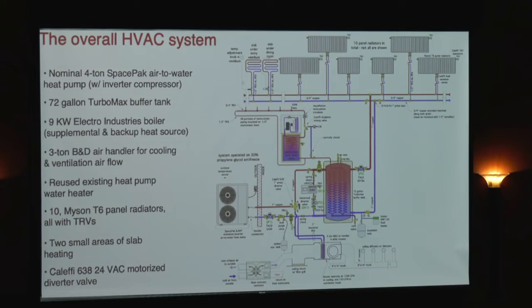So rather than do that, we had this girder that went right down the center line of the house, the full length of the house. It's a 12-inch deep laminated veneer lumber girder. You'll see it in just a minute here, basically we just hit the middle of that girder with 1-inch piping coming from the buffer tank here. This is 1-inch piping, and then we split it to both directions with 3/4-inch pipe, and then we just put T's in.